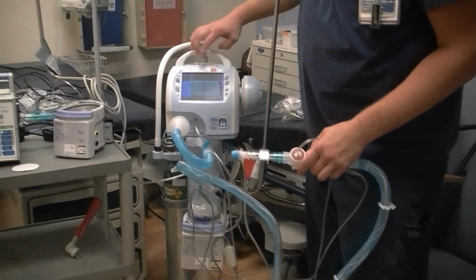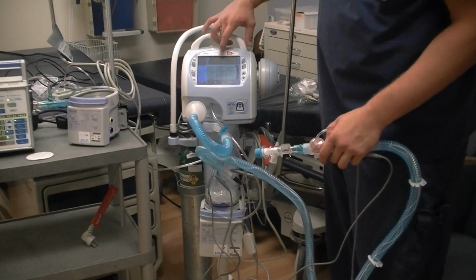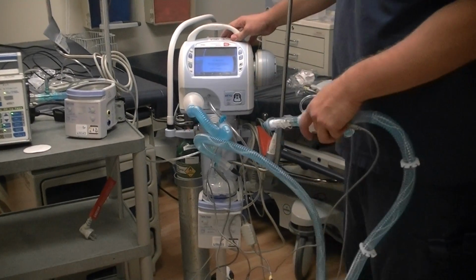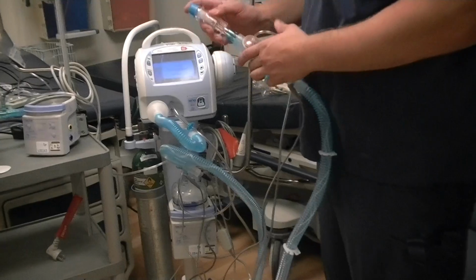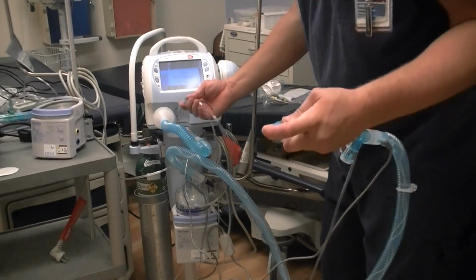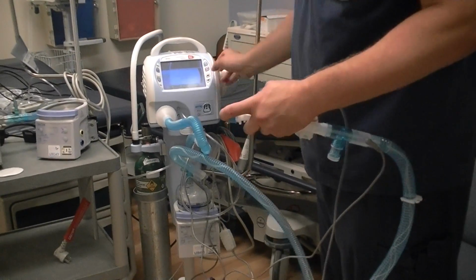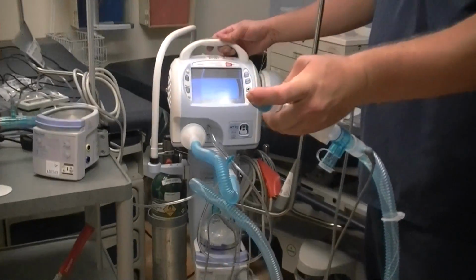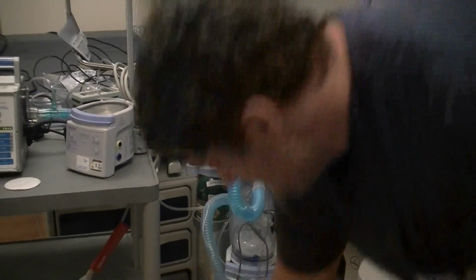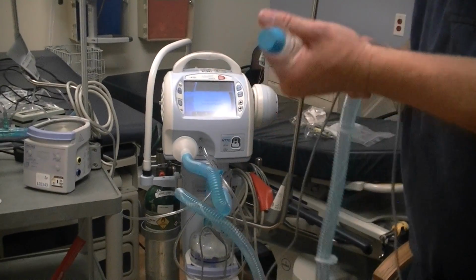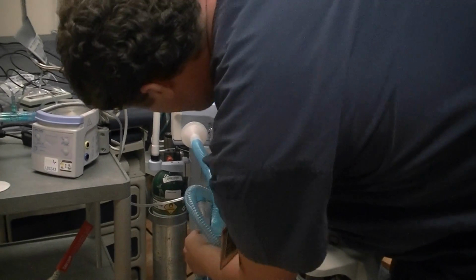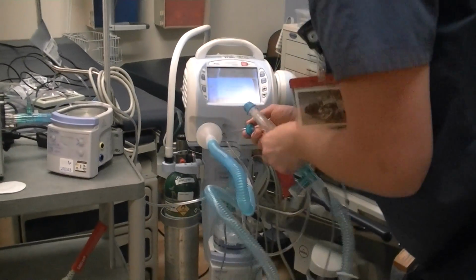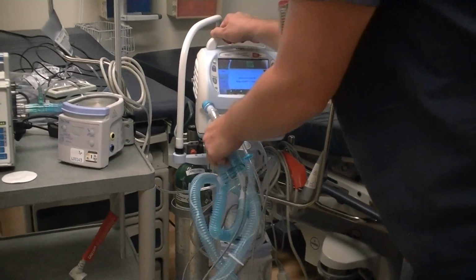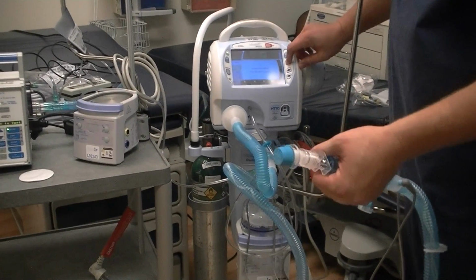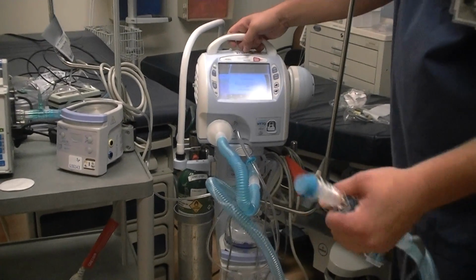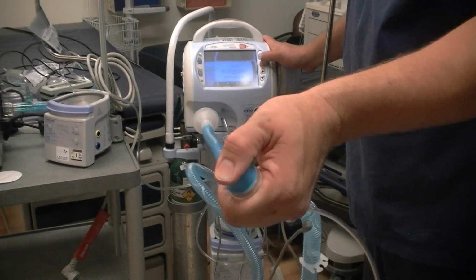To do your cal on this one, this screen will pop up when you first start it. Press circuit check and simply just follow the directions on the screen. It says occlude the patient, end of the circuit, and press accept to start. So we're occluded, we're all locked in everywhere, and we're going to press accept. We're going to run a circuit check. And I have a leak somewhere, I think. Yep. Whoops. So it said that it didn't pass, so I'm just going to retighten everything and make sure that we're good everywhere. I press accept, circuit check again, press accept, and we're going to occlude our circuit.